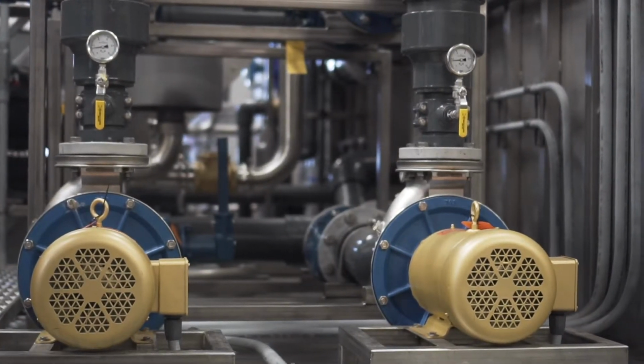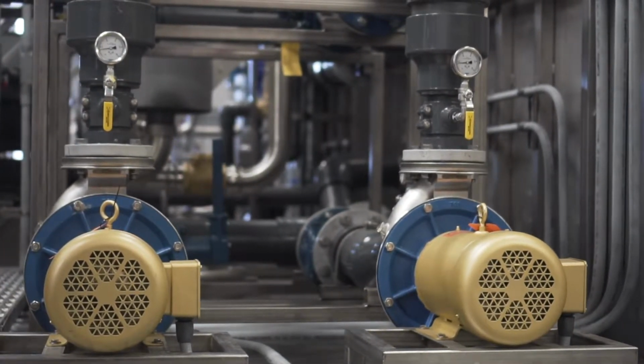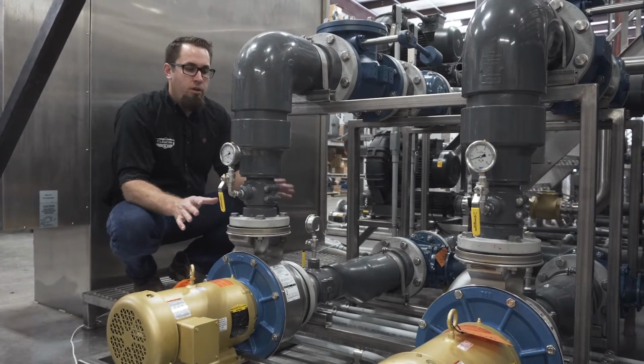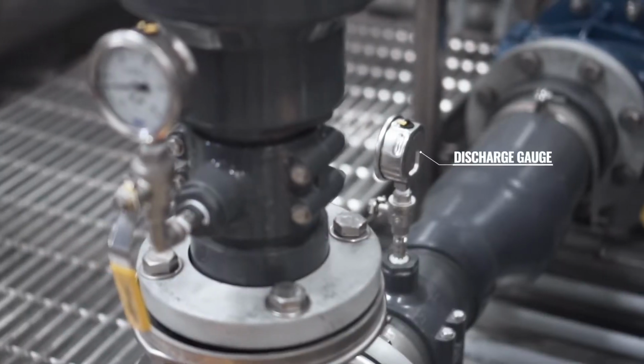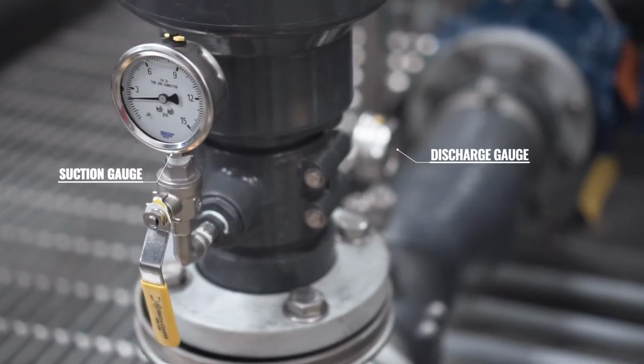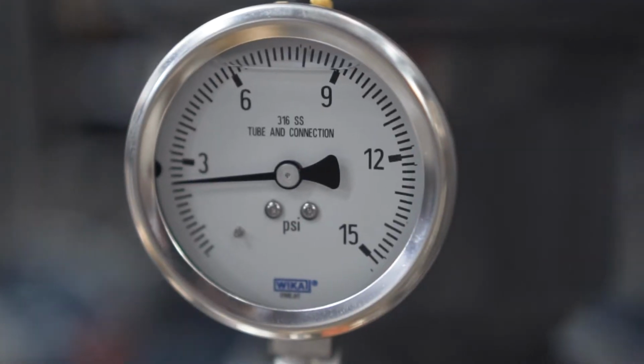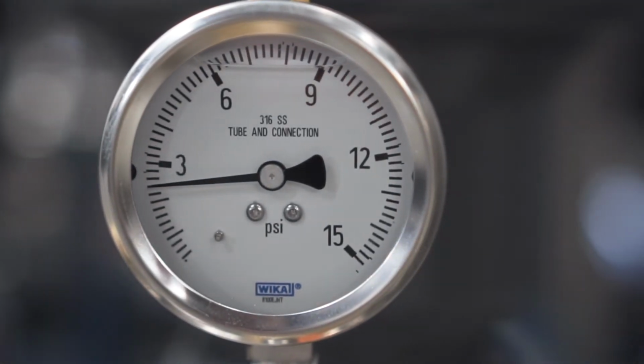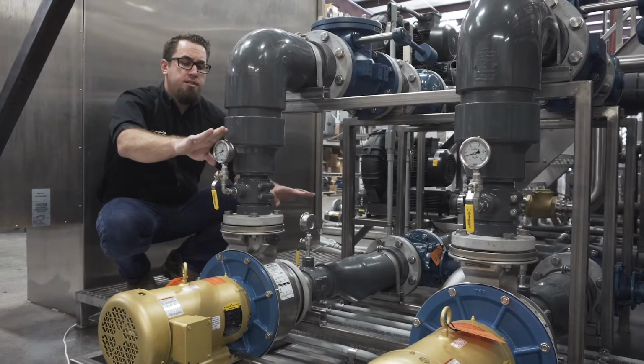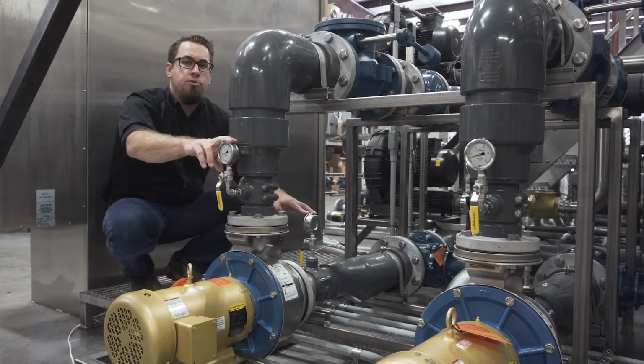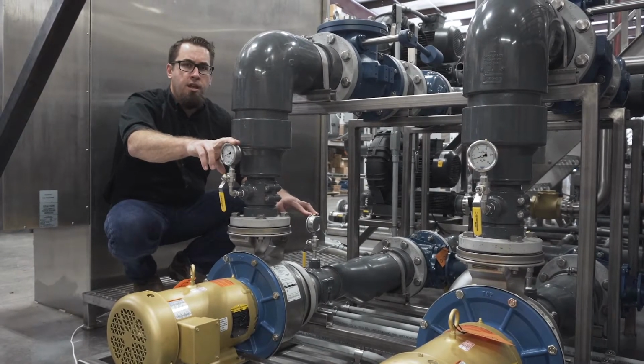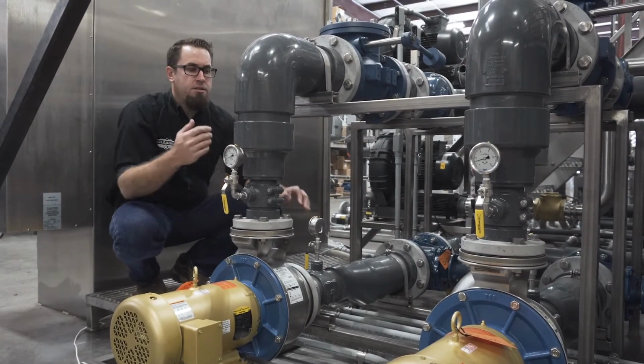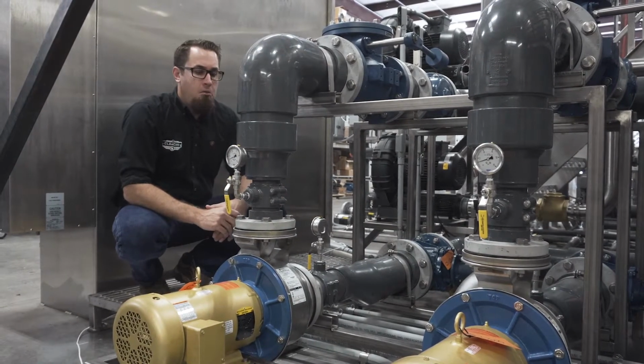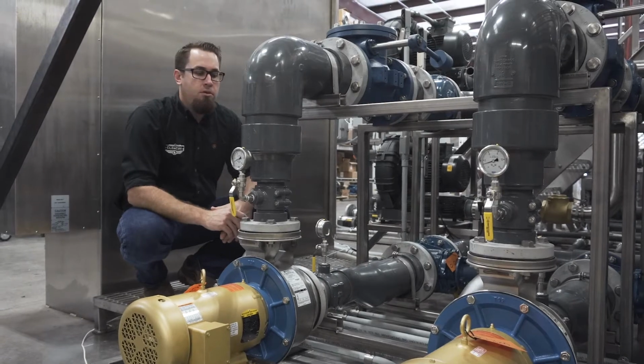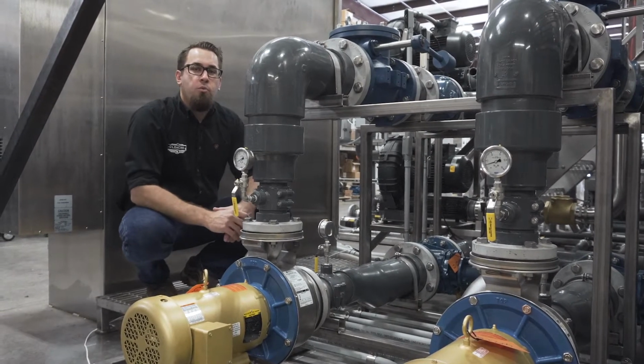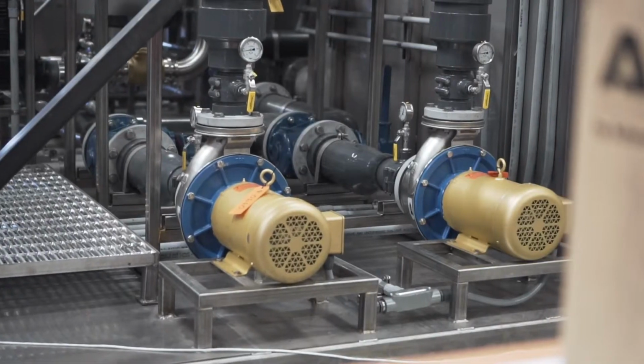Specifically, I wanted to talk about some of the features that are there for the operator and maintenance technicians. One of the first things you'll notice is there are gauges on the suction and discharge side of the pumps. This is to allow us to confirm where the pump is on its curve before it ever leaves, as well as this is an excellent troubleshooting tool for the operator or maintenance technician in the future to figure out if things are clogging, maybe the impeller's worn down, or you've got something going on where you're not actually getting the intended flow.